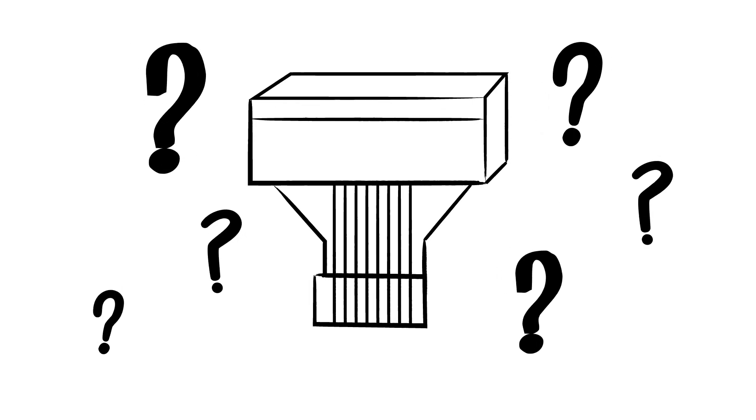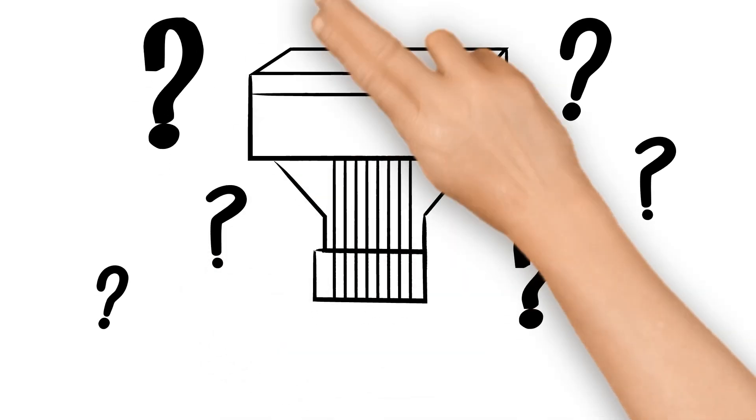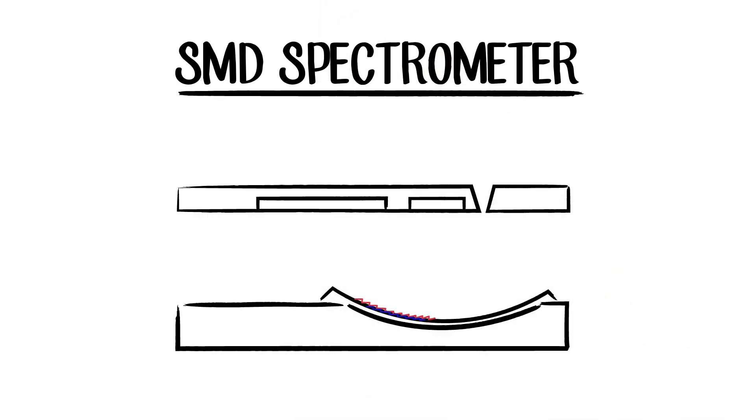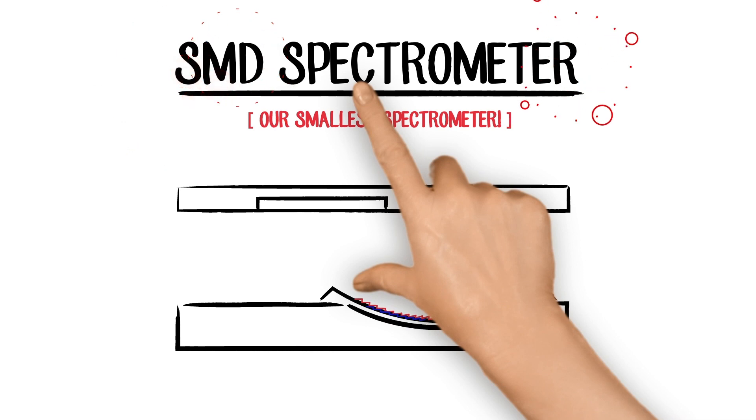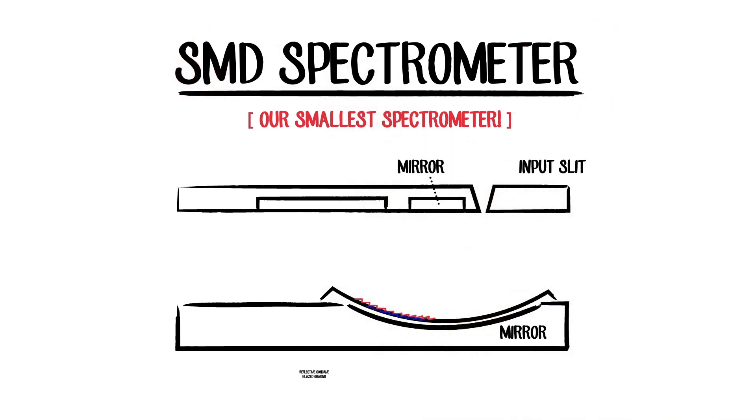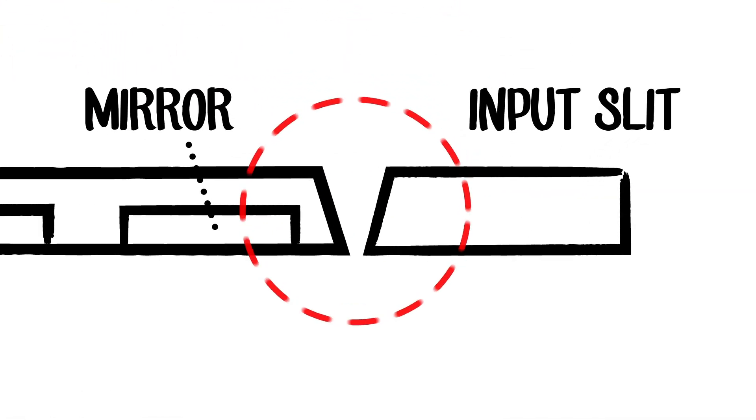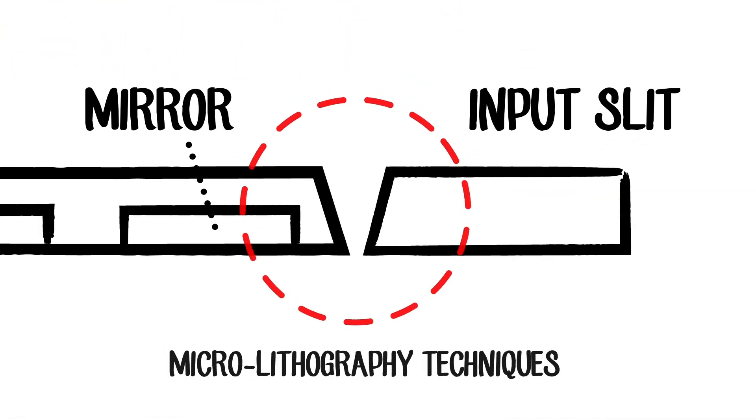So how do these extremely compact spectrometers compare to their larger predecessors? Similar to a typical spectrometer, our smallest spectrometer, the Surface Mount Detector or SMD spectrometer, contains an input slit, grating, and image sensor. What's cool is that the entrance slit is etched onto the CMOS image sensor using micro-lithography techniques.